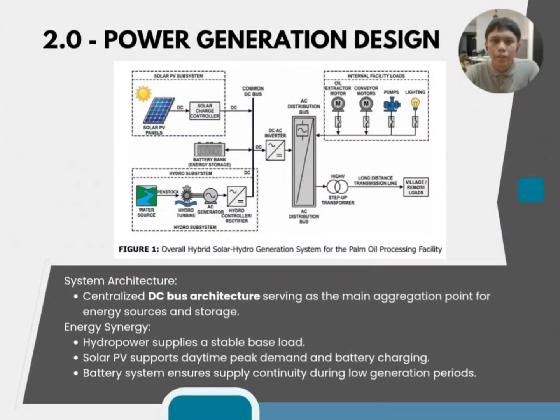So on this slide here, we have the next section 2.0, which is power generation design. This slide shows the overall system architecture of the proposed hybrid power system. The proposed system uses a centralized DC bus architecture to integrate multiple energy sources efficiently. Hydropower supplies a stable base load, solar PV handles daytime peak demand and battery charging, and the battery ensures continuous supply during low generation periods.